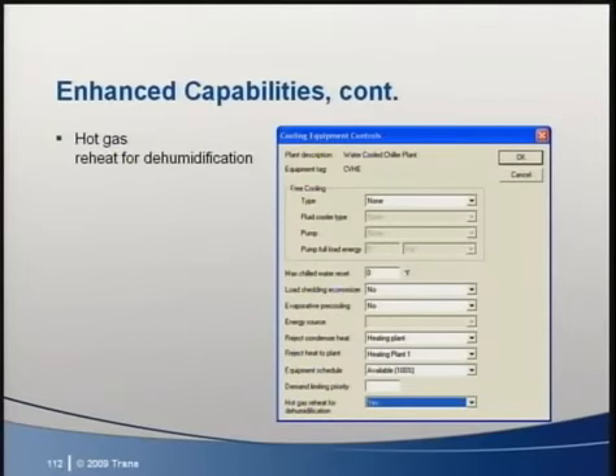There are a number of different reset strategies that can also be modeled. Whether it's humidity control for either indoor air quality standards or for the preservation of perishable items, hot gas reheat for dehumidification is available for unitary cooling equipment, including air-cooled unitary, water-cooled unitary, and water source heat pumps. This feature assumes that the associated airside system has a reheat coil located downstream of the cooling coil for dehumidification reheat purposes. As a heat rejection device, it cycles between the normal heat rejection condenser and a heat rejection setup that feeds to a dehumidification coil.